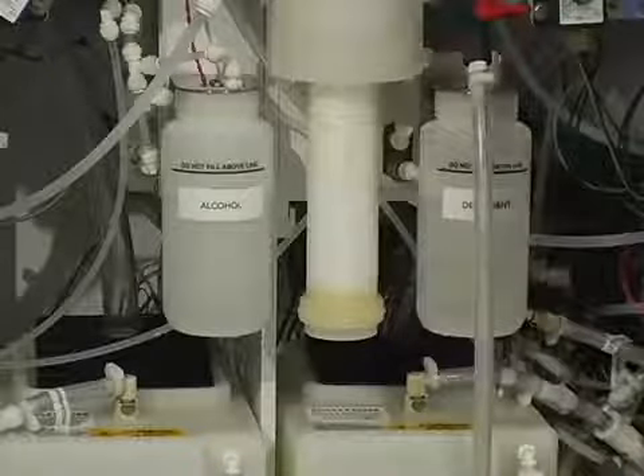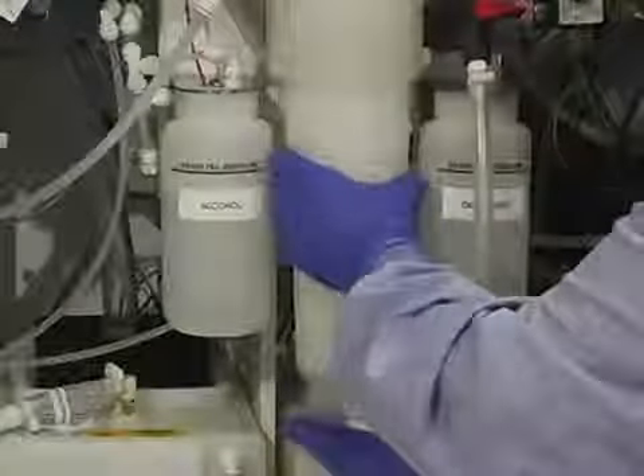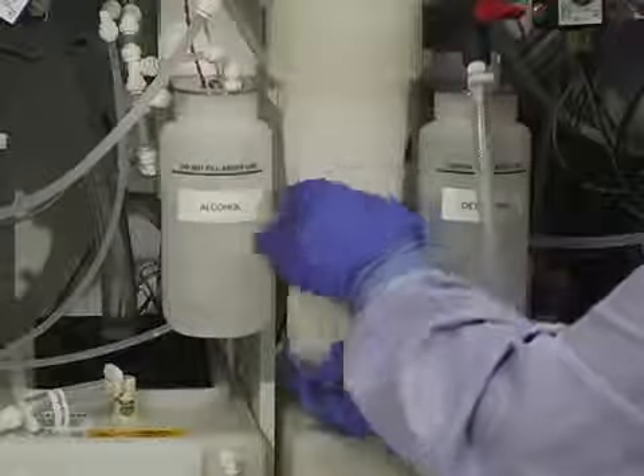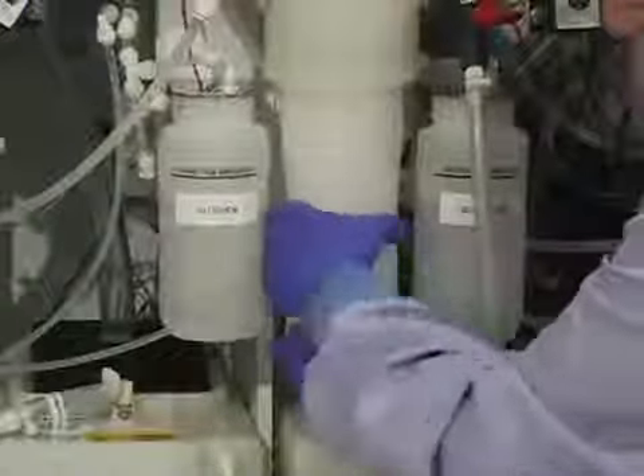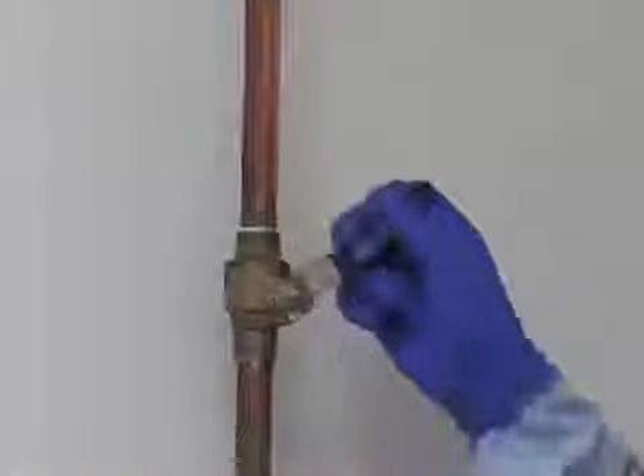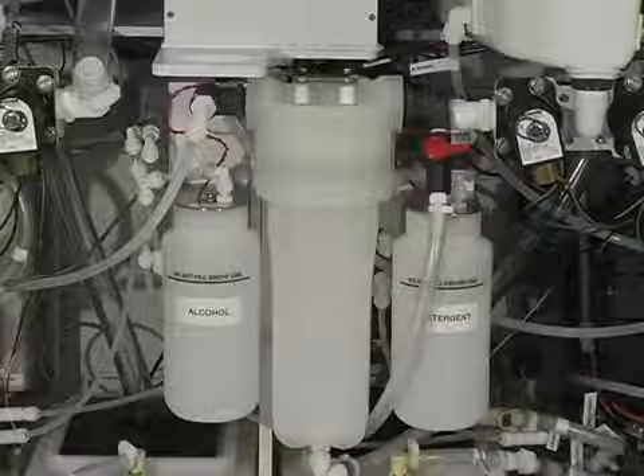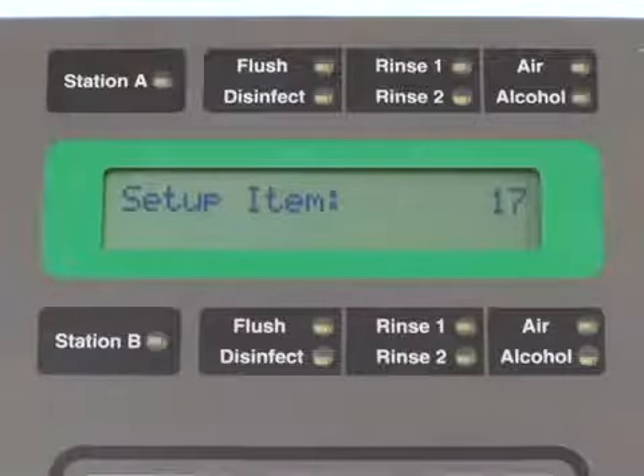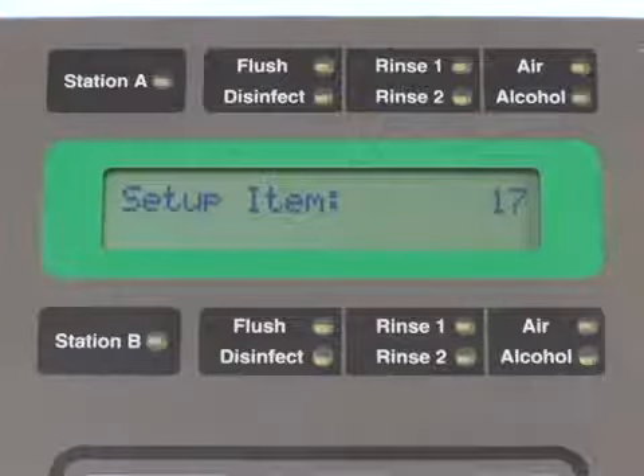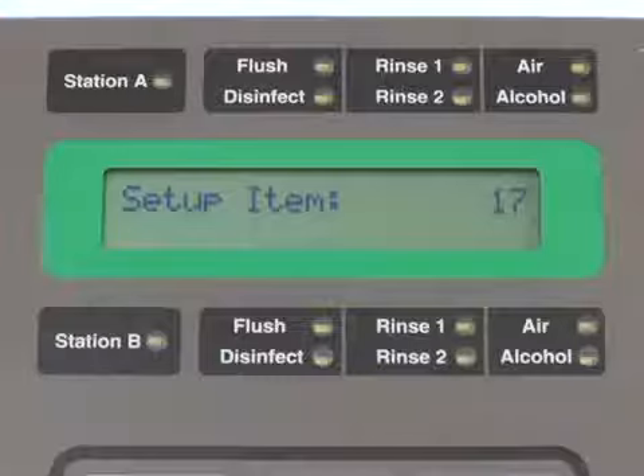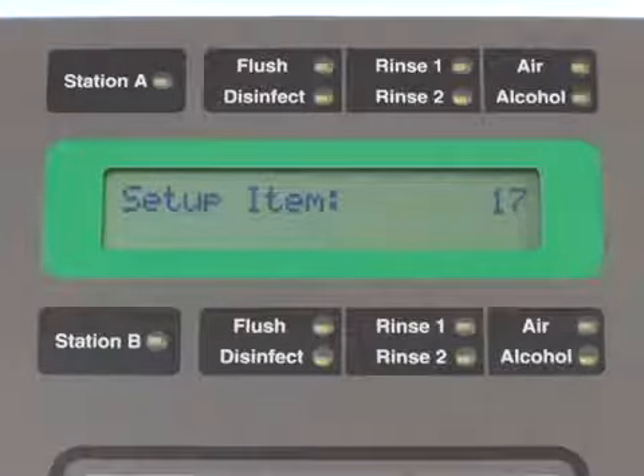Double-check the filter installation by pulling down on the filter cartridge to ensure that it's locked in place. Confirm that the housing O-ring is in place. Install the filter housing onto the cap. Hand tighten the housing. Close the bleed valve. Reconnect the water line and slowly turn on the water. As the water pressure increases, check for leaks. Proceed to treat the water lines. First, verify that the machine is idle by using Setup Function 17. Verify there is no time remaining in the cycle. Connect the basin restrictors that came with the reprocessor in both the A and B basins. This will restrict flow into the basin.